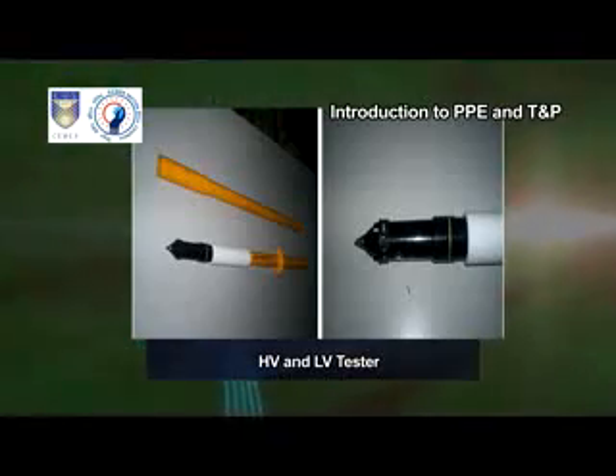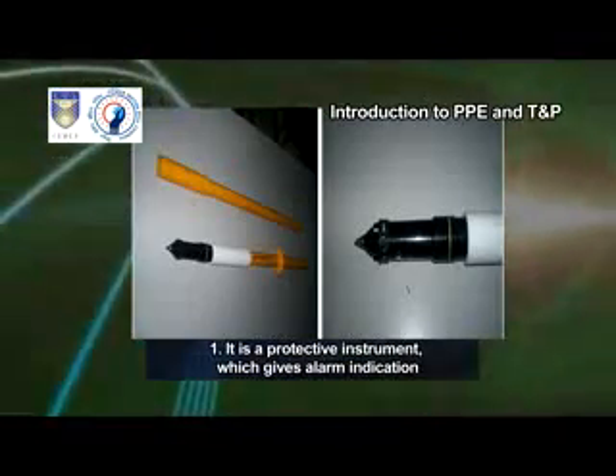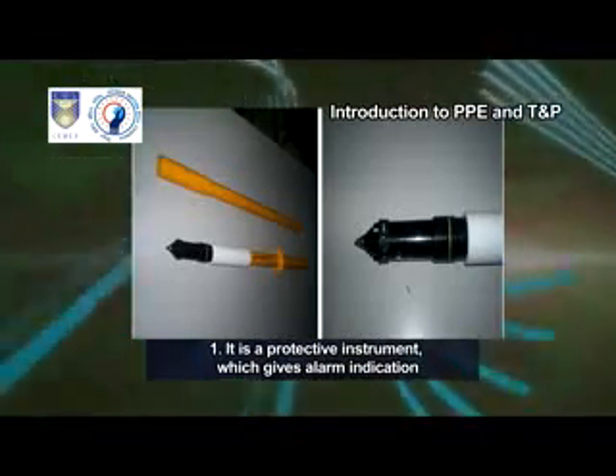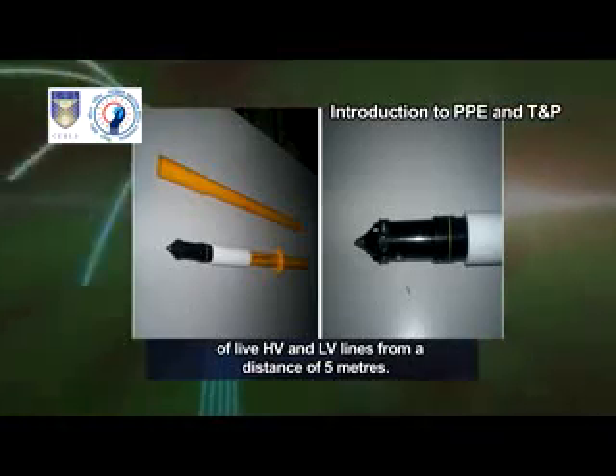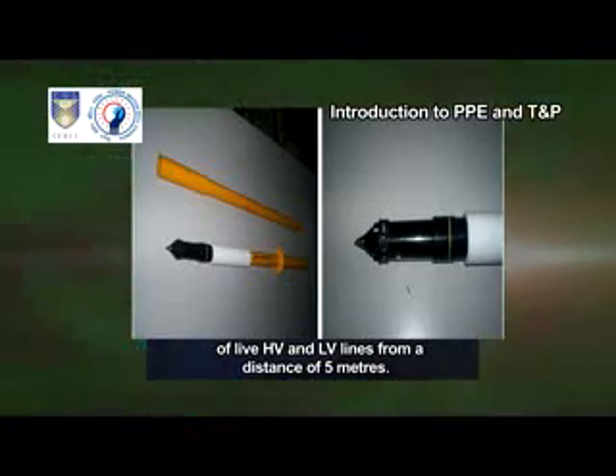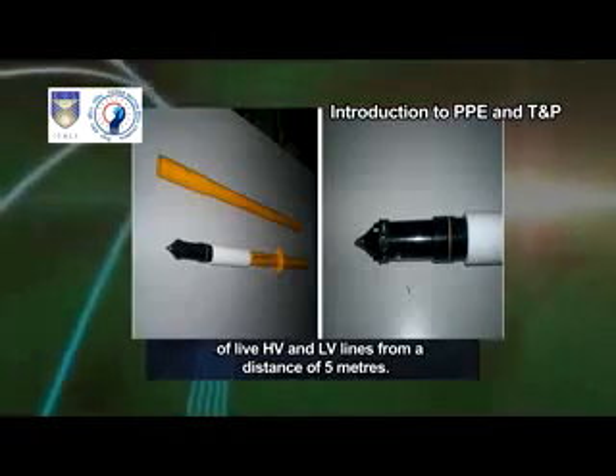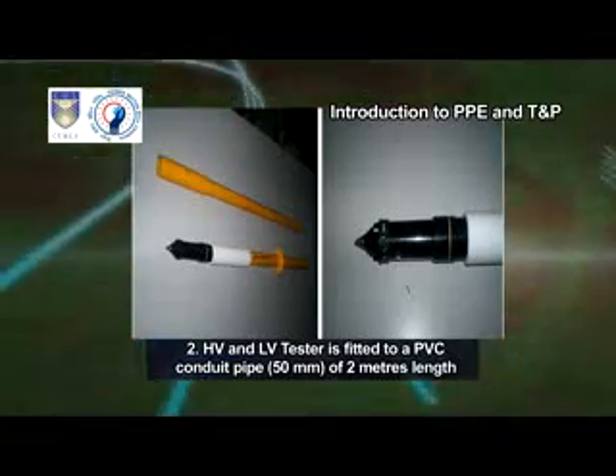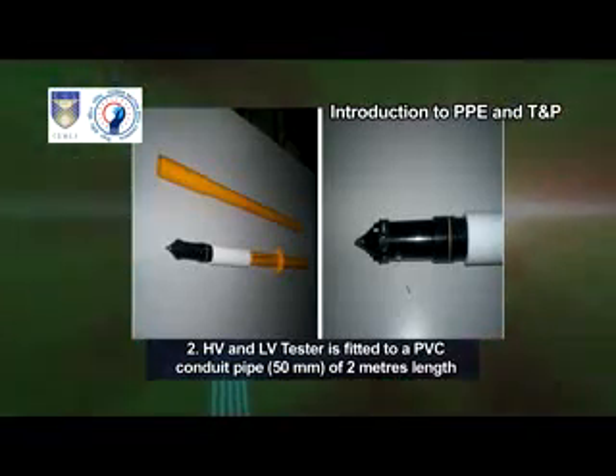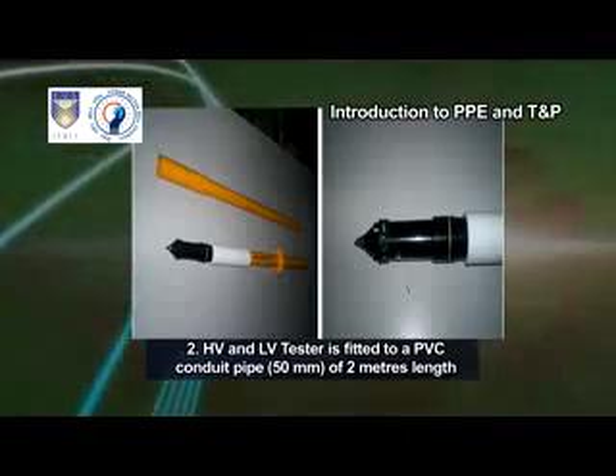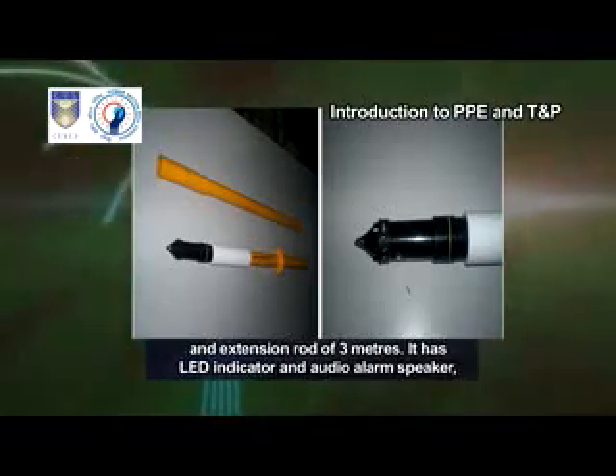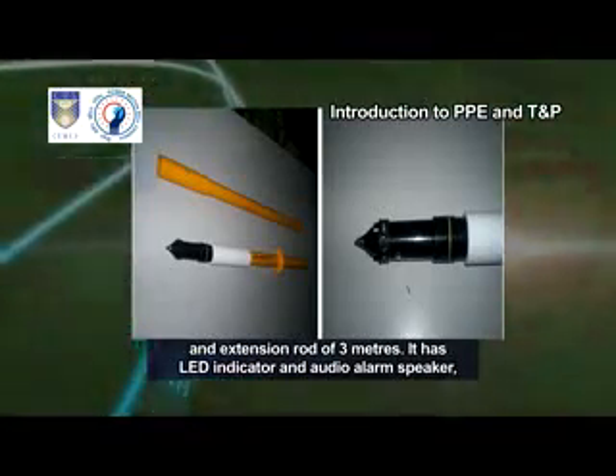HV and LV tester. It is a protective instrument which gives an alarm indication of live HV and LV lines from a distance of 5 meters. The HV and LV tester is fitted to a PVC conduit pipe 50 mm of 2 meters length and an extension rod of 3 meters.